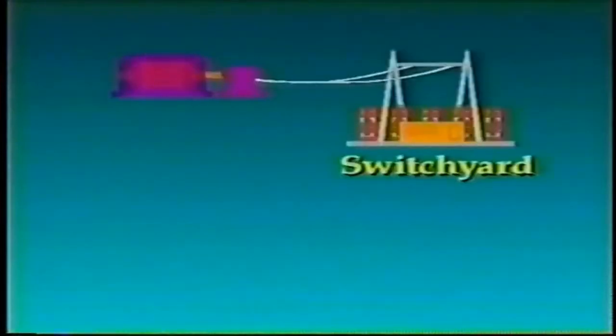Located a short distance from the power plant is a switchyard. From here, the flow of electricity is directed to individual transmission lines. Substations change the voltage to different levels for other transmission lines. Substations and switchyards are sometimes in the same location. Disconnect switches at either a substation or switchyard provide a safe means of de-energizing portions of the transmission system.